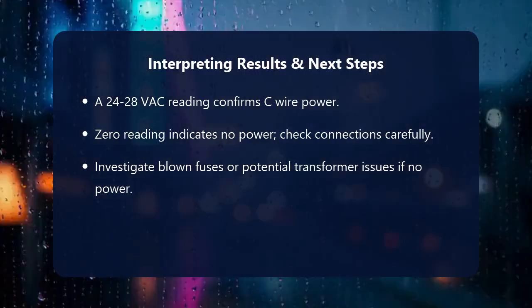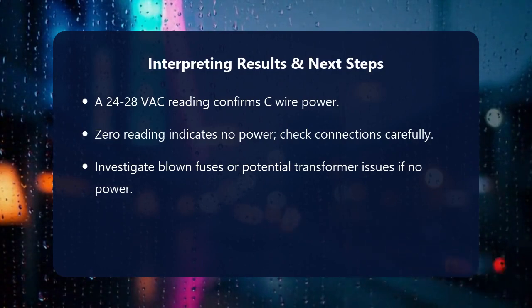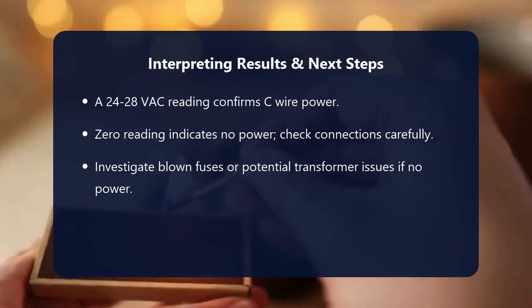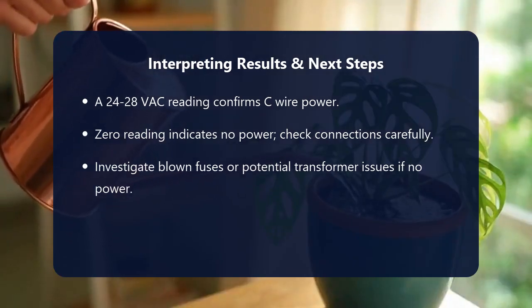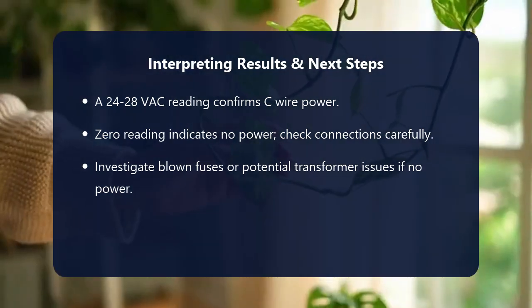You might also check for a blown fuse on the control board itself, as some boards have a small automotive-style fuse that protects the low-voltage transformer. If the fuse is good and connections are solid, the issue could be with the transformer itself, which would require professional diagnosis and replacement. Testing your C-wire for power is a straightforward process that empowers you to diagnose common HVAC electrical issues confidently. Always remember to prioritize safety by shutting off power before beginning any work.